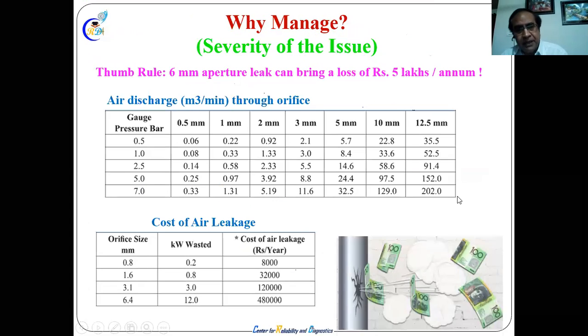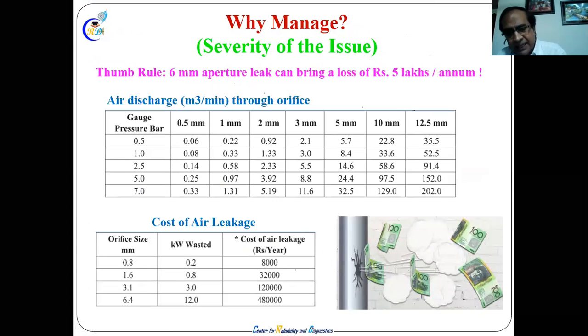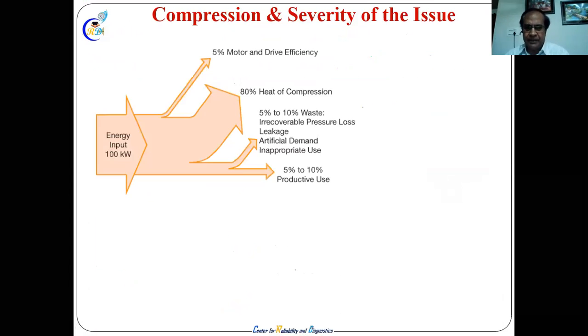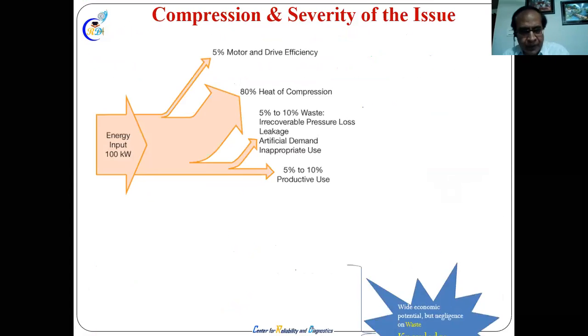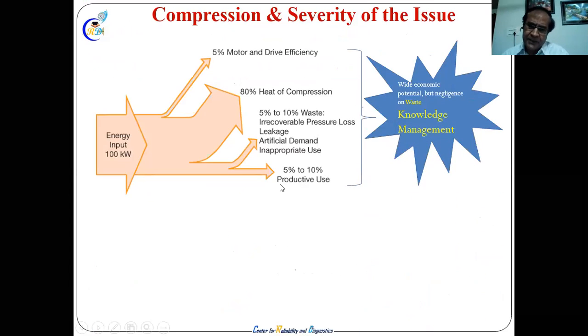So much energy, but we care very little about energy saving in compression, which has the widest scope for energy saving. In the compressor the severity of the issue is very high. We get only 5 to 10%. So awareness is a big issue. Leakage is too much. Nobody bothers about the leakage, and leakage is not visible as long as it is not giving a lot of sound. People don't care about it.